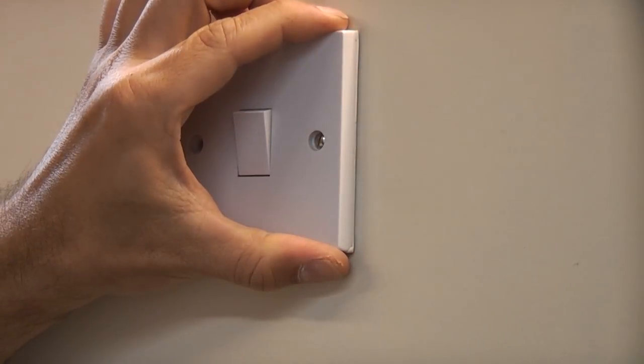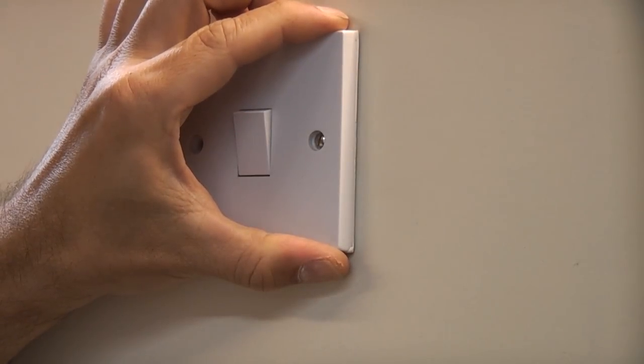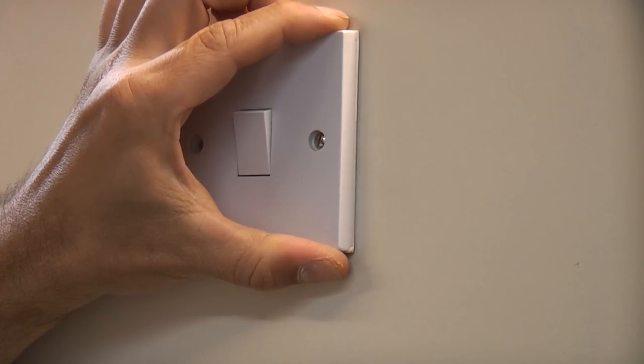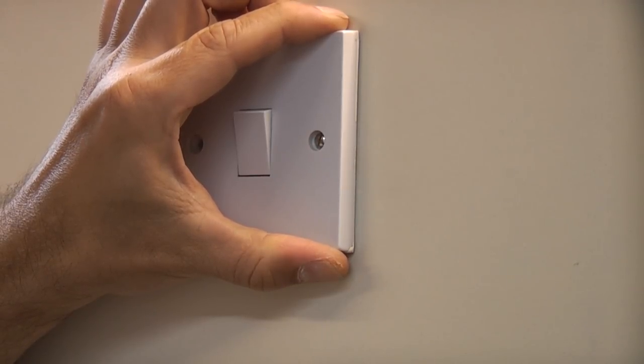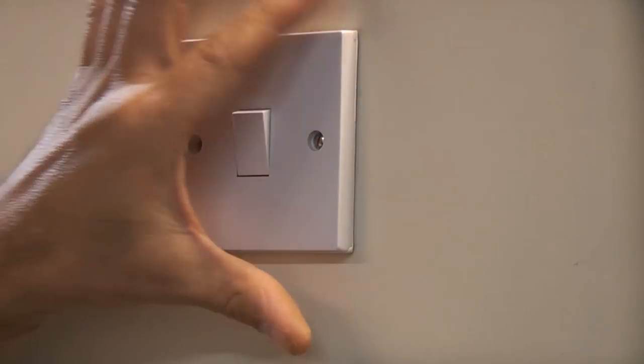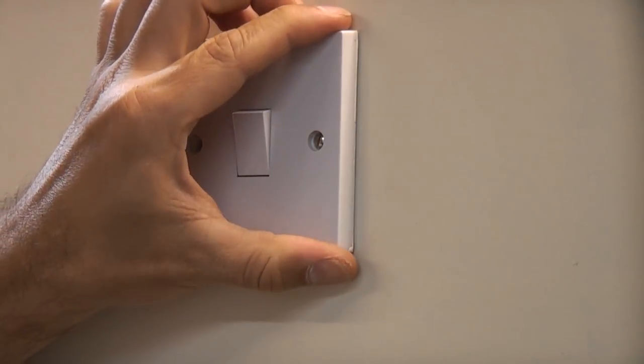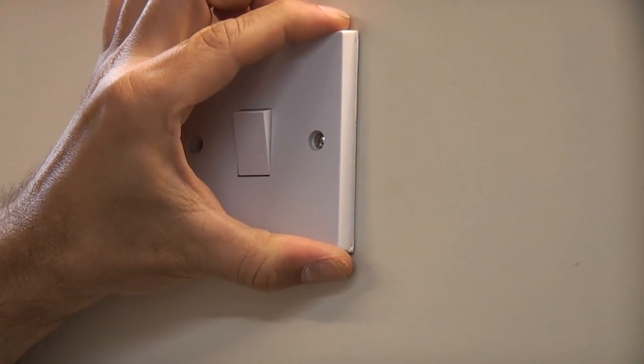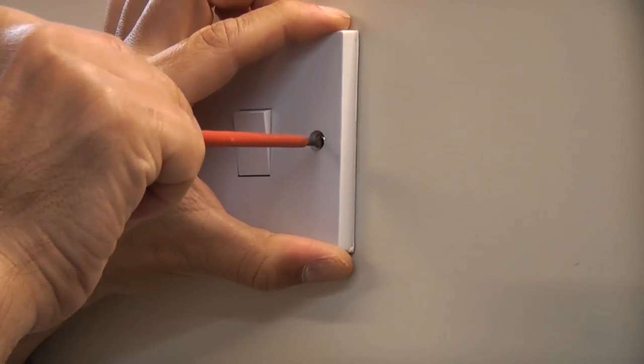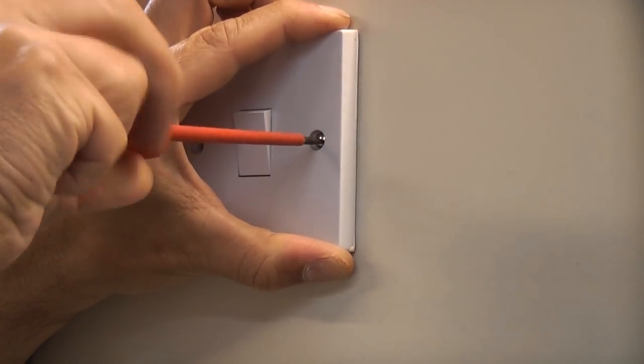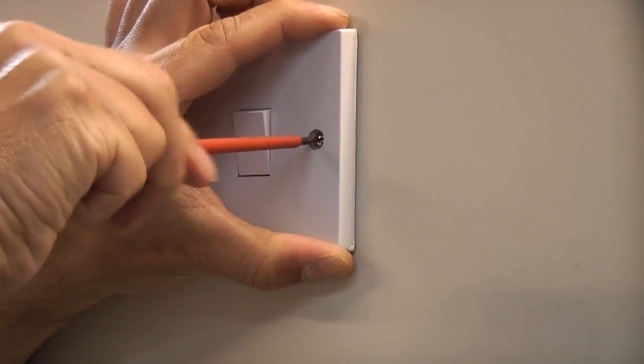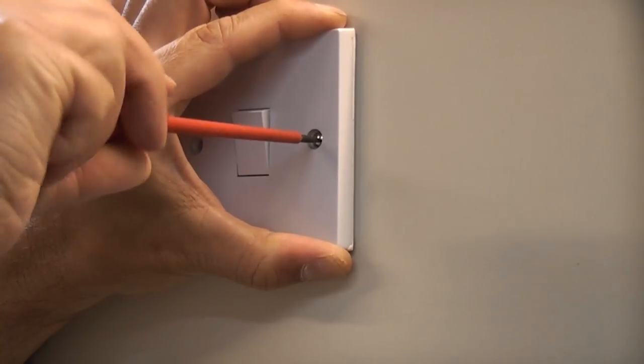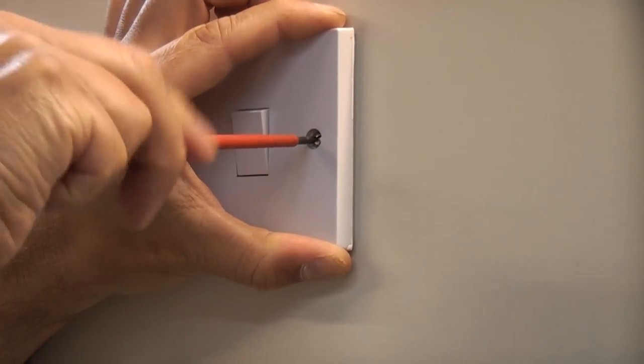Sometimes you'll find that the screw won't actually undo or tighten up because either the screw is stripped or the lug behind. To fix that you need to grab hold of the switch at the top and the bottom and pull on it with your finger and thumb whilst undoing the screw and in most cases that will actually undo the screw.